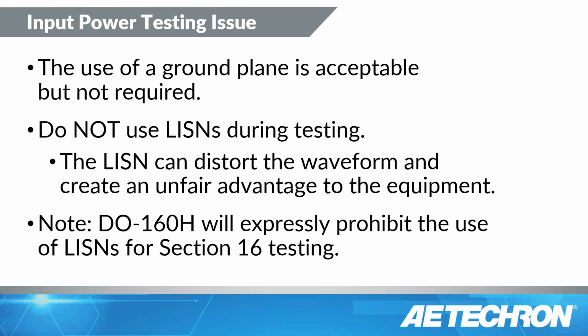Now for this type of testing, there's no requirement to have a ground plane, although it's acceptable to use one. The one thing that we recommend though is never to use an LISN on the power lines when you're performing this testing. The reason is that the LISNs can actually distort the waveform and create an unfair advantage or possibly a disadvantage to the equipment. In the revision of DO-160, DO-160H, which will likely be coming out next year, LISNs will be specifically prohibited from being used in Section 16.